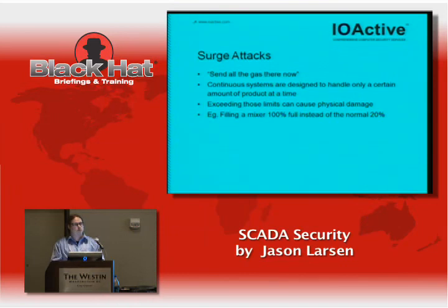We actually got a pretty good surge attack out of it. One of the first things we found when we started playing with the system was that the pumps filling the holding tanks at the top of the process could pump stuff in faster than the drain at the bottom of the tanks could handle it. So we filled it full of simulant, cranked the pumps all the way up, and the tanks overflowed over the top. Unfortunately, the engineers had put a bunch of the actual electrical operating equipment below these holding tanks at the top of the thing, gravity fed, and lots of stuff shorted out.